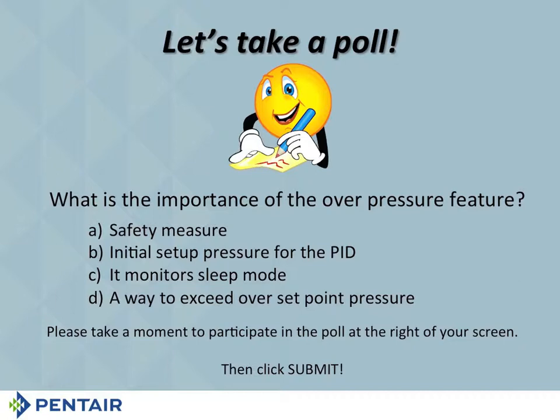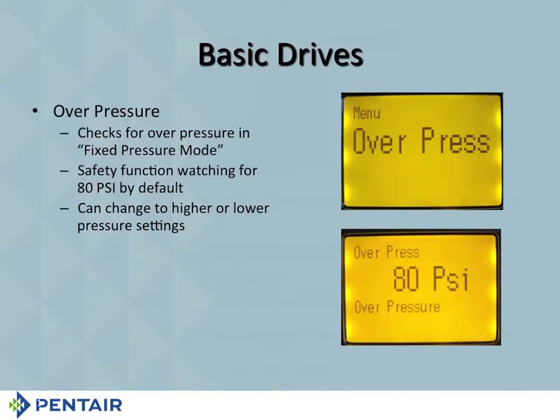And so we want you to understand that in PID mode, all the overpressure does is it watches to see what's taking place. If I go more than 20 pounds over the set point pressure, it's going to shut the drive down. I will tell you this, you need to change that if you change your set point pressure. I had somebody call me up one time and they say, I don't get it. I set the set point pressure at 90 and it keeps going off at 80. It won't get to 90. What's going on? And so I said to the guy, are you at the drive now? He said, yes.